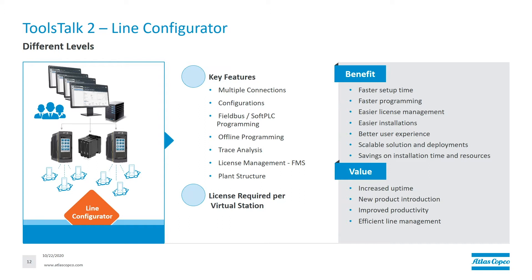Next is Line Configurator, which is similar to Station Setup where you could do everything — configurations, soft PLC, and field bus mapping. The additional functionality is a plant structure, meaning every controller is connected to your server and you could jump between controllers and copy-paste programs. You could also manage your licenses through FMS: if you want to rebalance your line — for example, Controller A has six tools and Controller B has one — you could move those tool licenses from A to B. This is licensed per virtual station, so if your plant has six tools connected to the server, you need six licenses of ToolsTalk 2 Line Configurator, with an unlimited number of users.